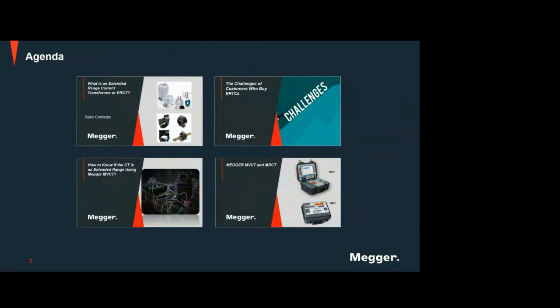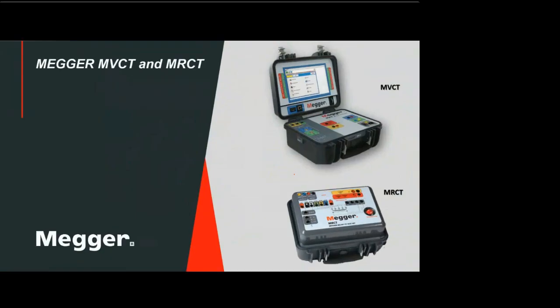All right. Now, introducing to you our Megger instruments for determining or verifying an ERCT. We have the MVCT and the MRCT. The difference between the two is that for the MRCT, you get the 2 kV transformer here. So meaning to say it is heavier, because it weighs around 37 pounds, while the MVCT is only 18 pounds, right?